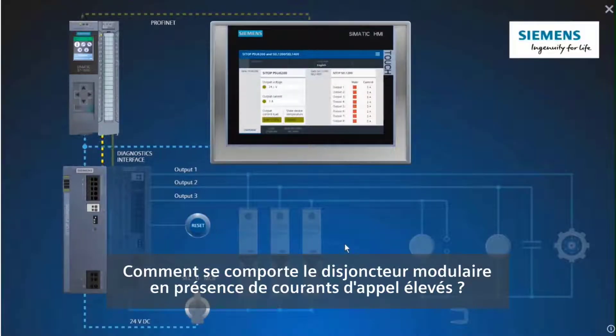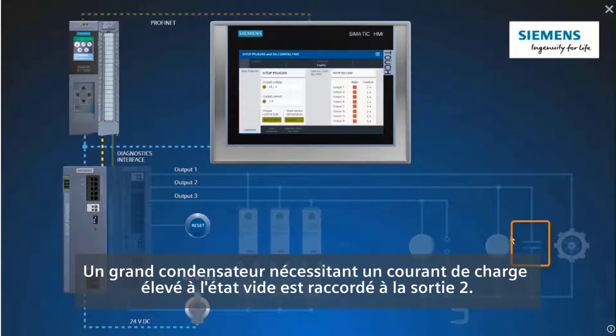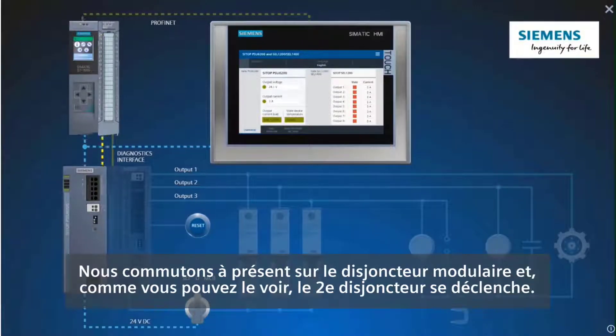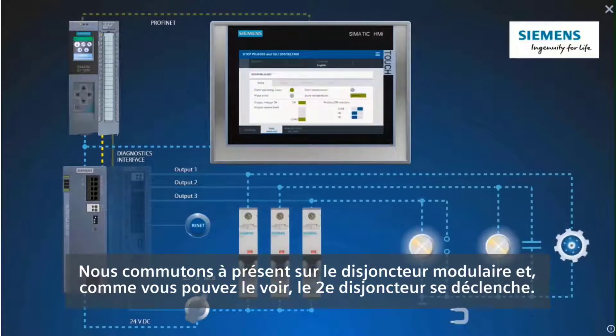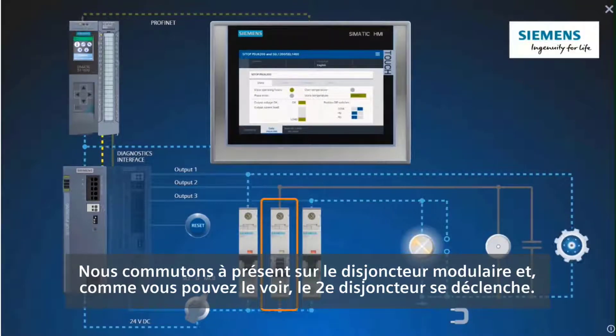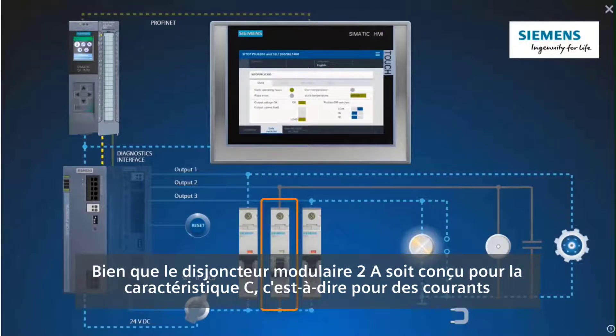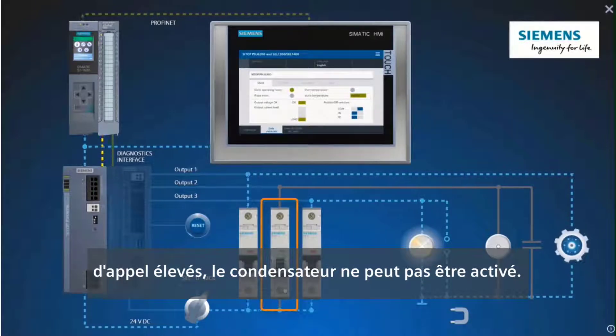How does the miniature circuit breaker behave in the case of high inrush currents? A large capacitor, which requires a high charging current when empty, is connected to output 2. Now we switch over to the miniature circuit breakers and, as you can see, the second circuit breaker trips. Although the 2A circuit breaker is designed in characteristic C — that is, for high inrush currents — the capacitor cannot be connected.